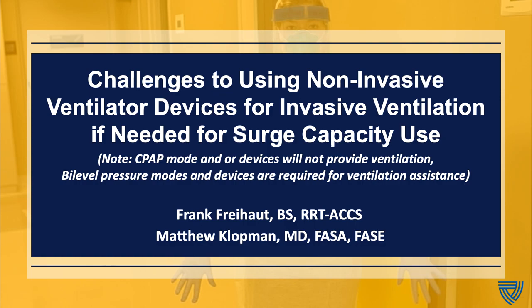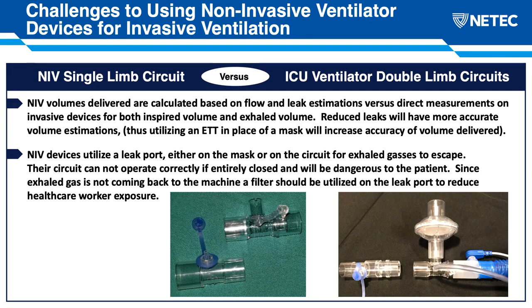And I'm talking about the bi-level devices, the BiPAPs. And so there are some differences that I'll just quickly review, and things to consider if you're going to use a non-invasive device for invasive ventilation. One of the big things you gain, obviously, is less leak because you're not utilizing the mask and the leaks around the mask, and you can hook right to the ET tube.